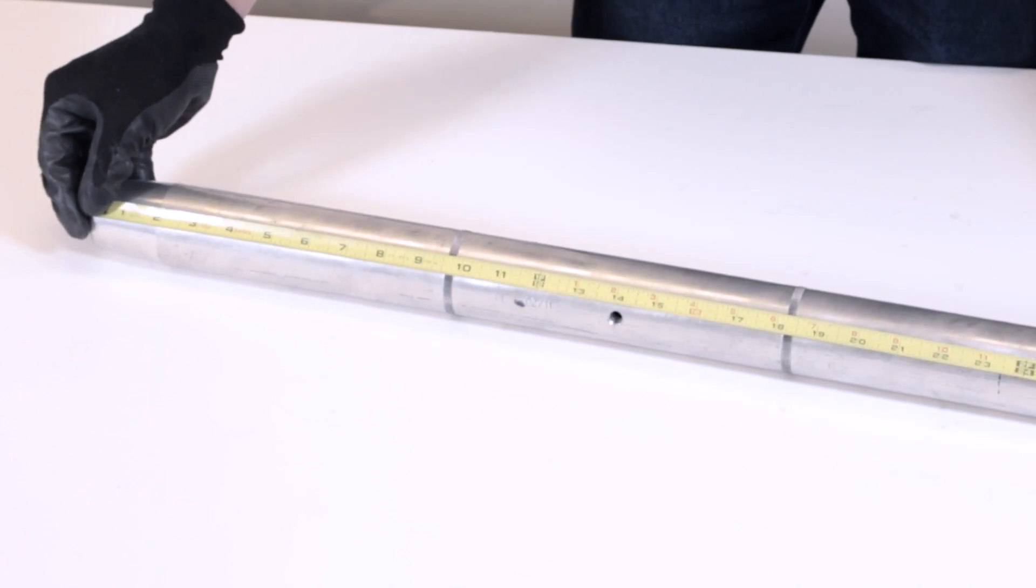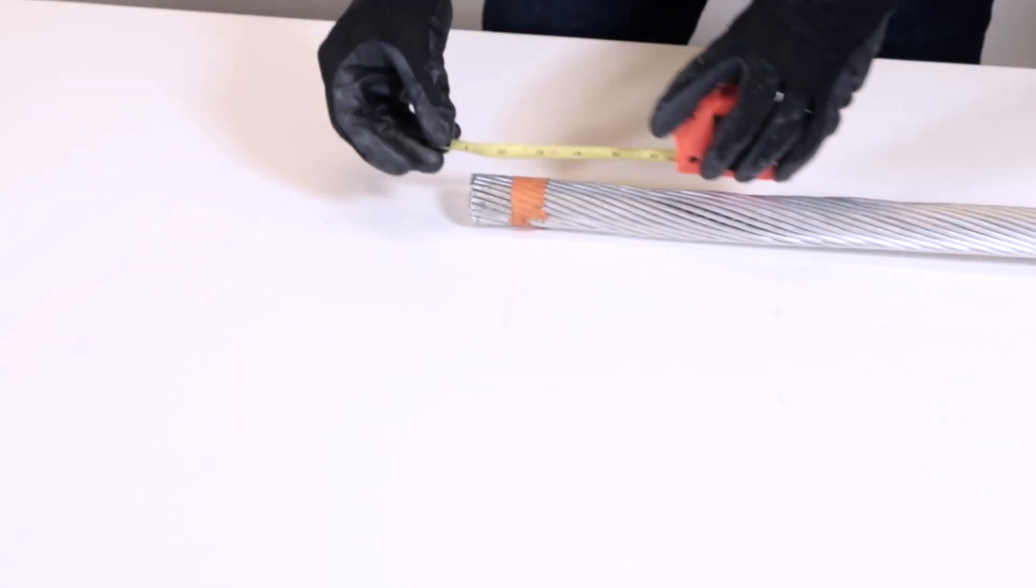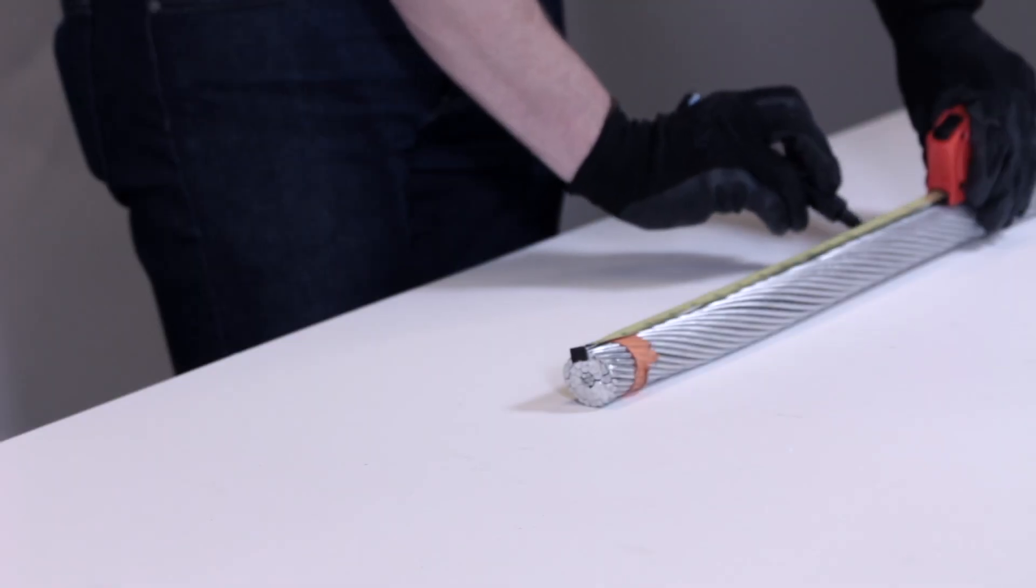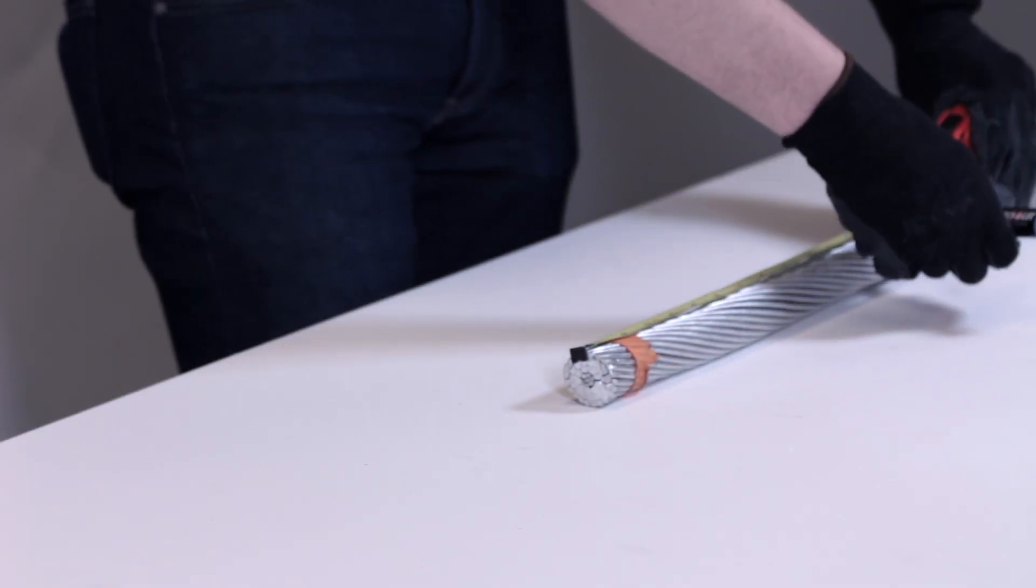Measure the length of the aluminum splice body. Measure and mark half this length on the conductor from the cut strand ends. This mark will be important later when centering the splice.